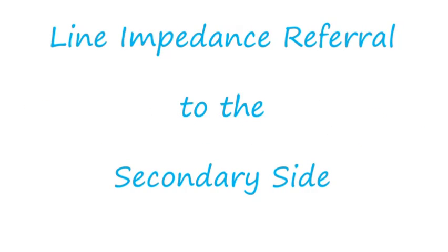In this video, I'll show how to refer line impedance from the primary to the secondary side of the relays, because relays are used to protect transmission lines, and the inputs to the relays are CTs and also voltage transformers.